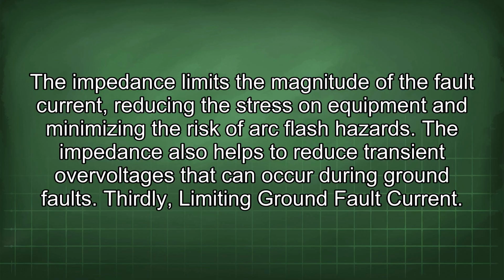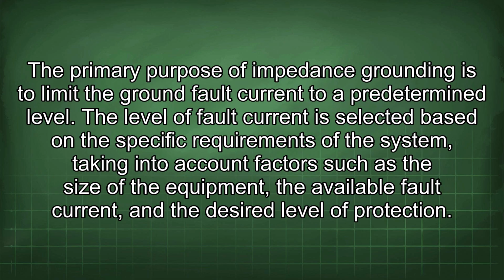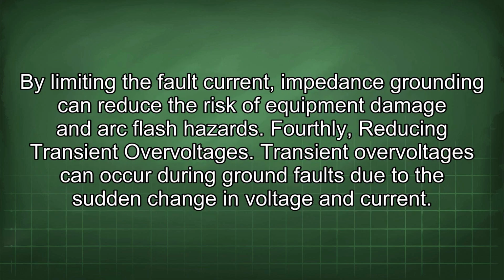Thirdly, limiting ground fault current. The primary purpose of impedance grounding is to limit the ground fault current to a predetermined level. The level of fault current is selected based on the specific requirements of the system, taking into account factors such as the size of the equipment, the available fault current, and the desired level of protection. By limiting the fault current, impedance grounding can reduce the risk of equipment damage and arc flash hazards.